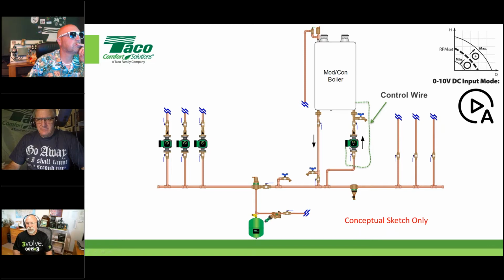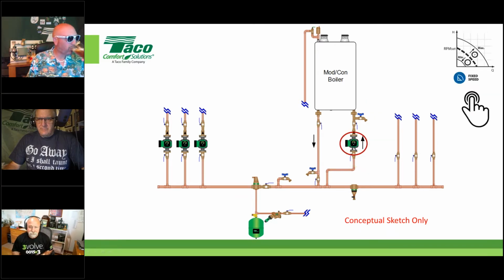But our littlest pump right now, and you'll see where I'm going with that emphasis on littlest pump, doesn't have the ability to receive that in an ECM offering yet, okay? And since we've all kind of graduated to the high efficiency circulators, I'm making note of that. Taco by all means does have a circulator that receives the 0 to 10, but oftentimes it's actually bigger than you need. And that's what we'll get into in my short little session tonight. So we're focusing on this circulator in that configuration.